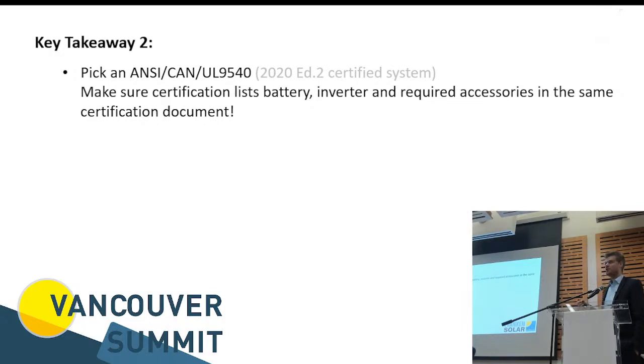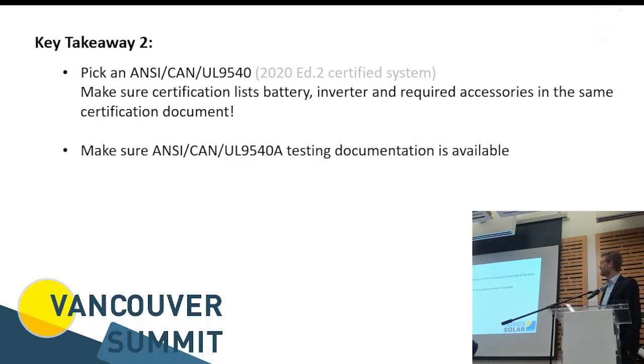And the documentation needs to list all components. Some documentation on the market only lists the battery and all kinds of battery variants, but the inverter is missing, or the cabinet is missing, or wiring instructions are missing, and parts that are being used. Then you are also not compliant, because it's not a system at that point. It's just documentation for one component. And as we learned, a system certification is the entire system and not just one component.